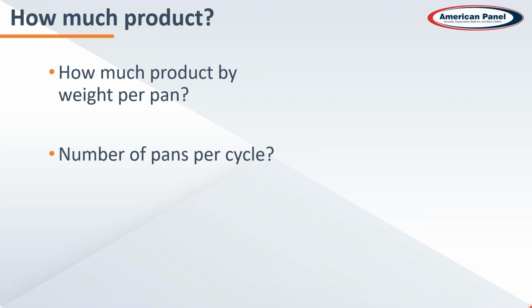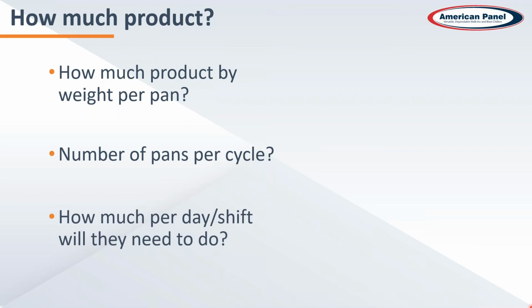How many pans per cycle are they going to need to want to do? Another one of the sizing factors of our chillers is going to be the pans. How many pans can get physically in that unit? And then how much per day or per shift are they going to need to blast chill? You're probably going to have to do some math here. If the customer tells you they're going to do 300 pounds a day, they're going to do 1,200 pounds a day, they're going to do 50 pounds a day. All that's important to know in figuring out the correct product to steer them towards.